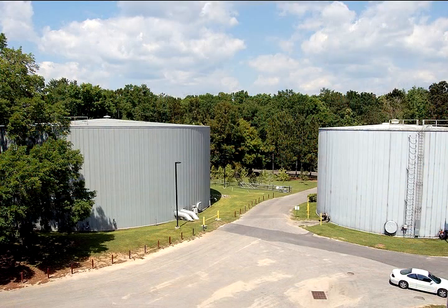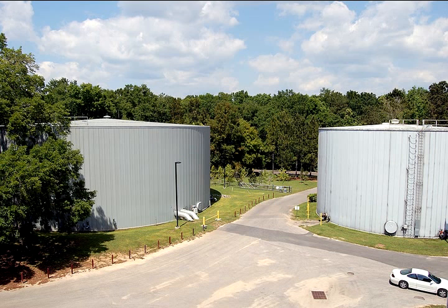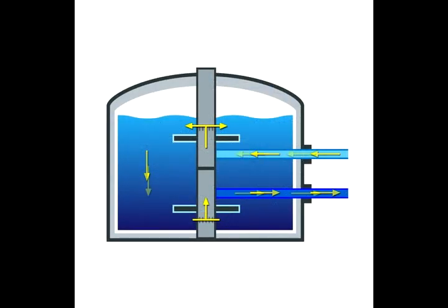So we have these two chilled water storage tanks here out back. Those are like thermal shock absorbers. I store about 4 million gallons of 42 degree Fahrenheit water in those tanks. Equivalent to about 6 to 7 Olympic sized swimming pools. It gives me a very good, very fast means of removing heat from those magnets.